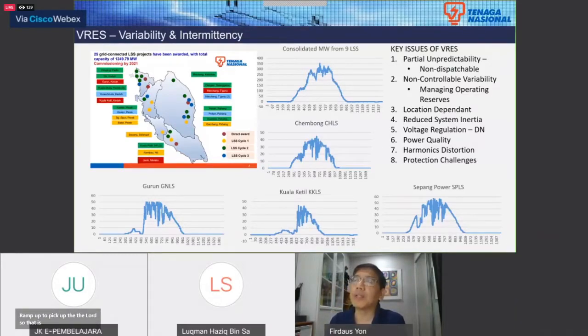Our current rule is that we must have enough spinning reserve to withstand the loss of the largest unit. Our largest unit is 1000 megawatts, so theoretically we should have 1000 megawatts of spinning reserve. Now, spinning reserve is actually a waste, because you're burning fuel for something to turn for no reason.